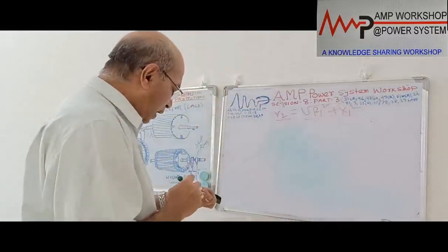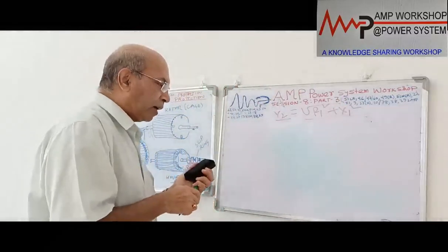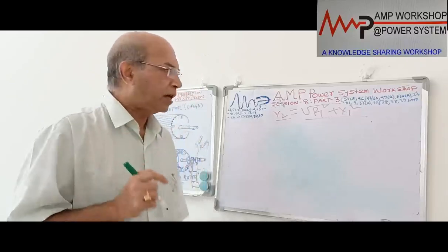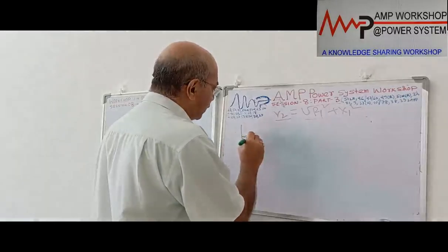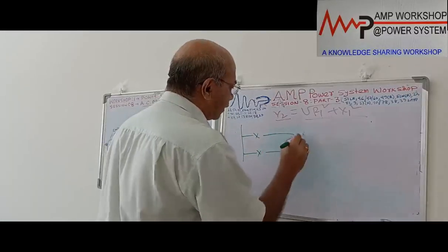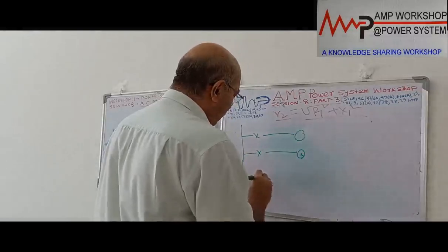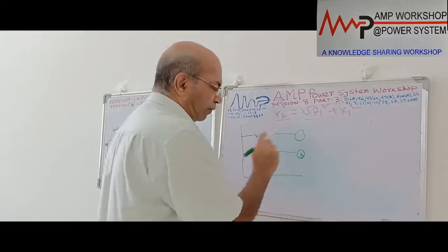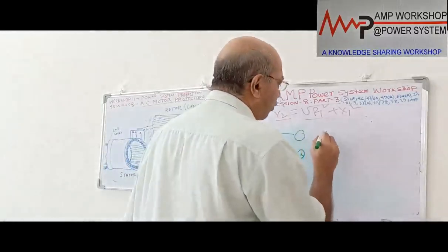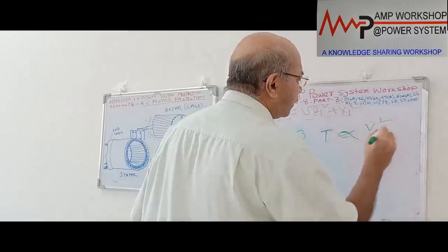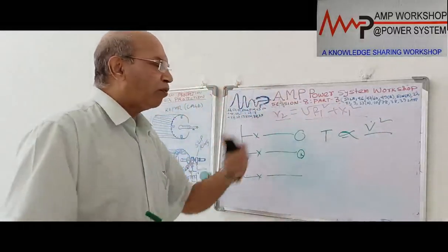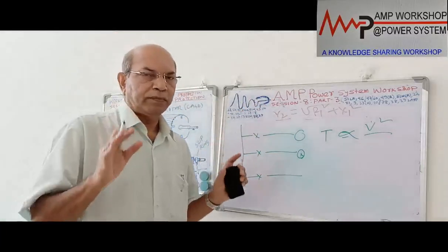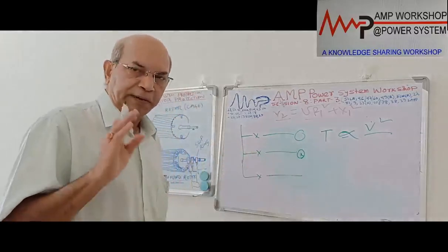Now the next point is under voltage protection. Motor under voltage protection is very important, because when there is an under voltage in the motor, two things can happen. Suppose multiple motors are connected to a bus. Suddenly there is an under voltage in the system and the motors stop, because we know the torque produced by the motor is proportional to the square of the voltage. If the voltage goes down, the torque produced will be less, so it may not be able to deliver the required torque and the motor can stop. But the motor is not disconnected from the system.